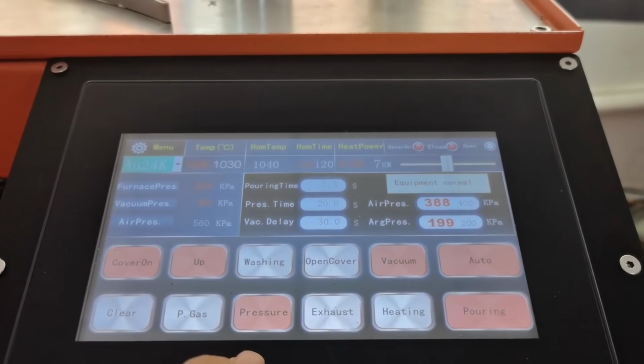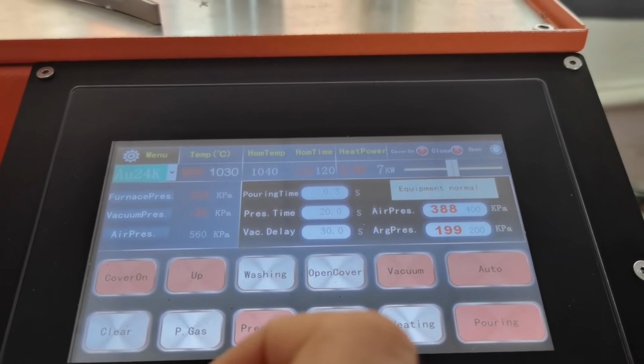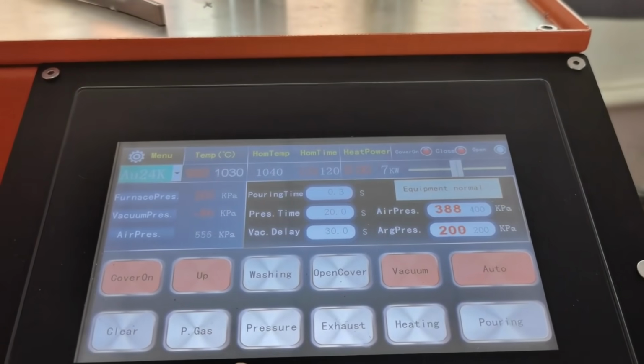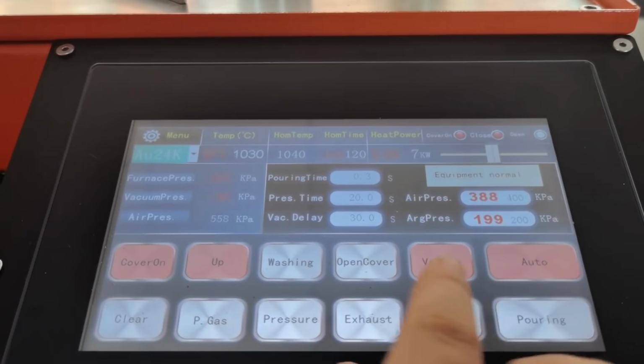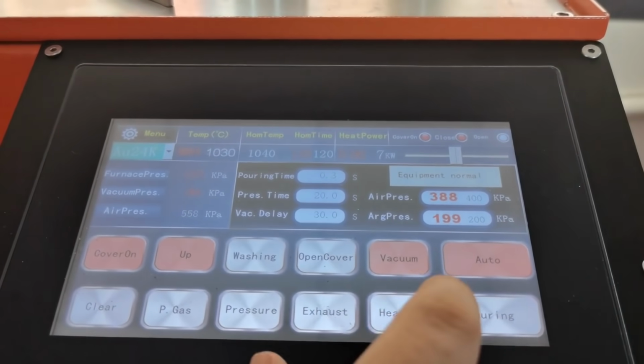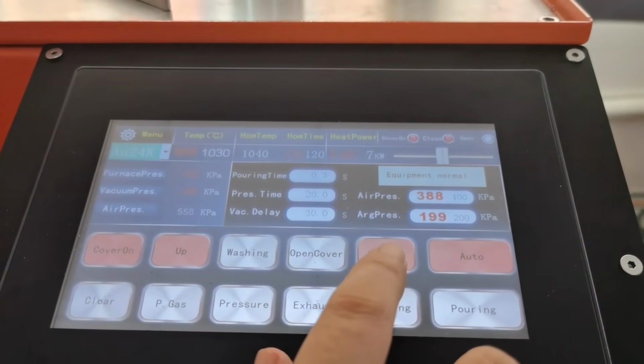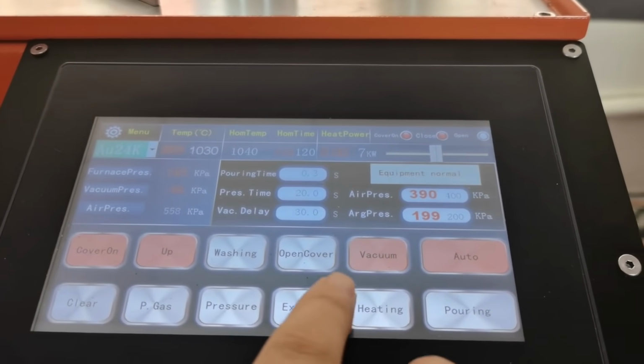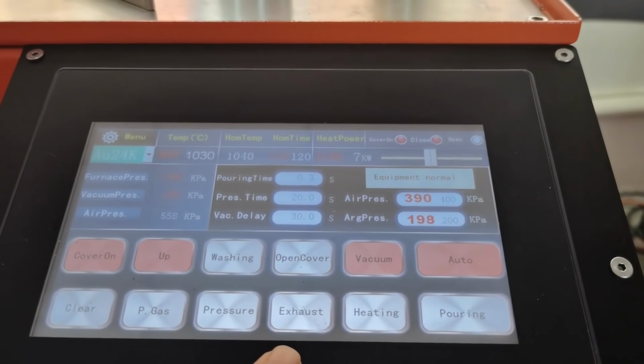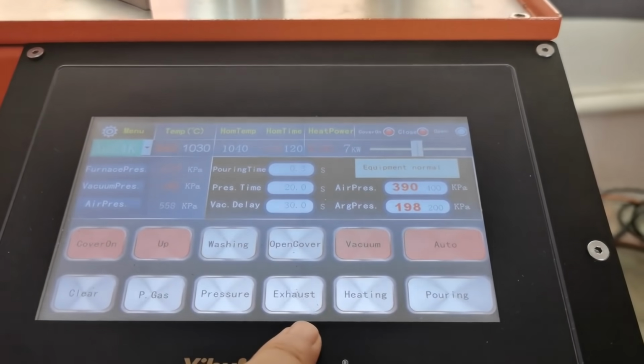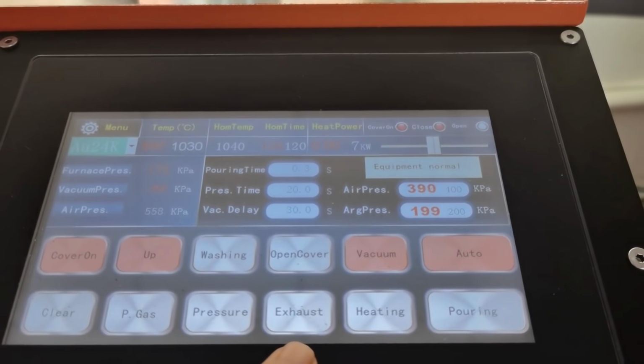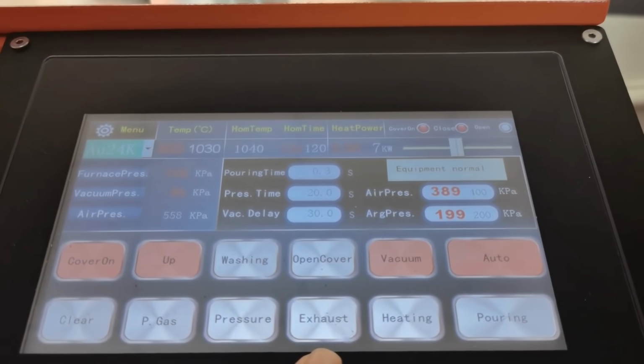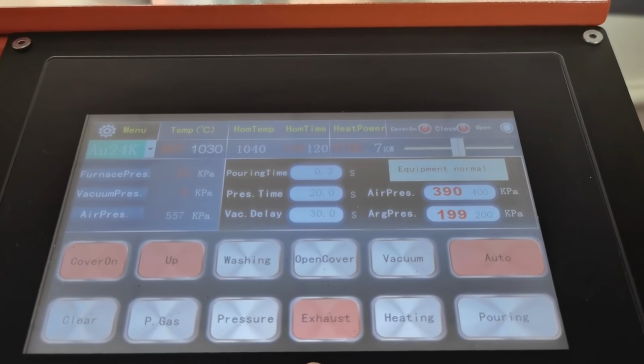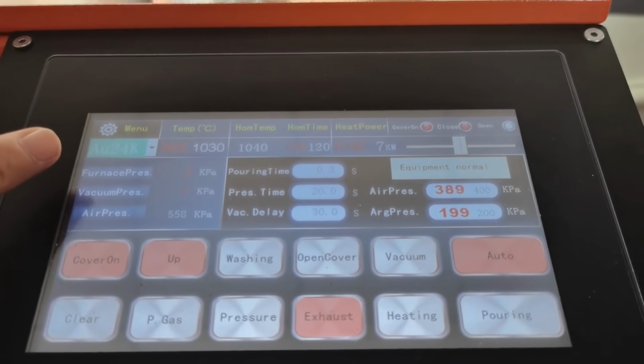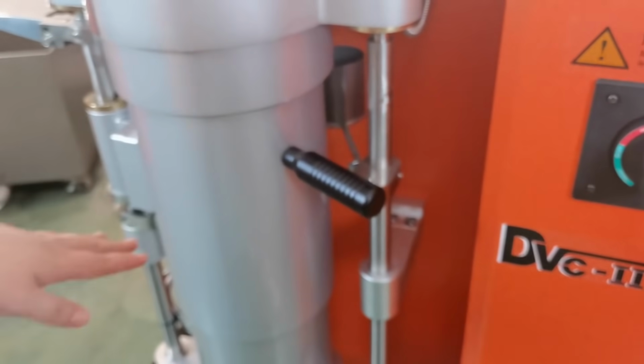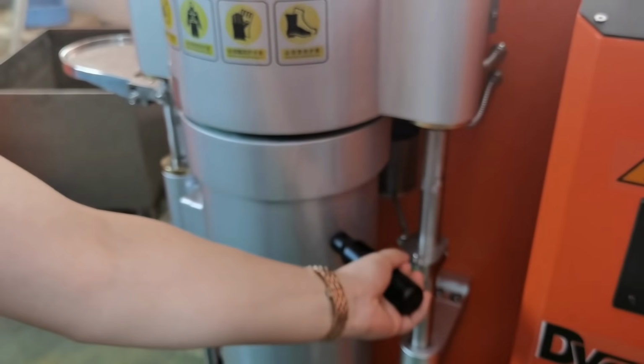After the pressure finishes, the vacuum will continue. Now we wait for the pressure. Okay, pressure finished, but the vacuum will continue working for 30 seconds as we preset. Now we wait. Still vacuum. Once the vacuum finishes, the system will start exhaust automatically. Now let us see the screen carefully to see the button changing. Still vacuum. Yeah, now the system starts exhaust. Once we see here the pressure becomes atmospheric pressure, the down chamber goes down automatically, right? Yes. Now we can move the down chamber back to the left.